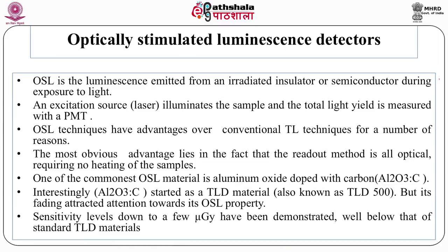A new category of detectors which has become popular nowadays is optically stimulated luminescence detectors, or OSLDs. What is optically stimulated luminescence? It is the luminescence emitted from an irradiated insulator or semiconductor during exposure to light. So unlike TLD, where you needed heat to produce light from the trapped energy of the radiation, here you use one wavelength of light to excite the material to emit another wavelength of light.